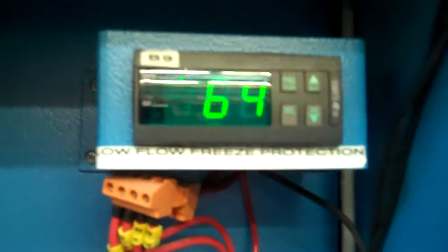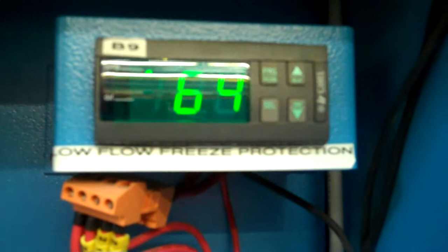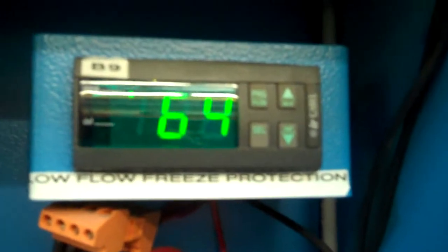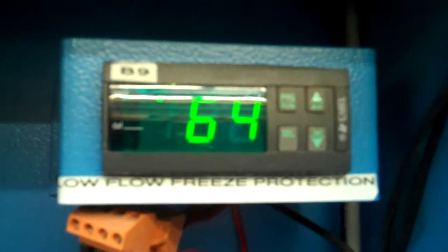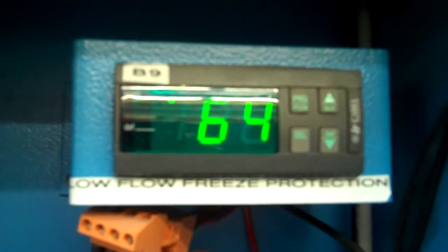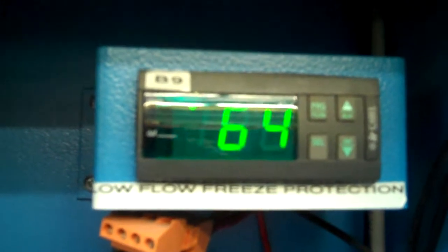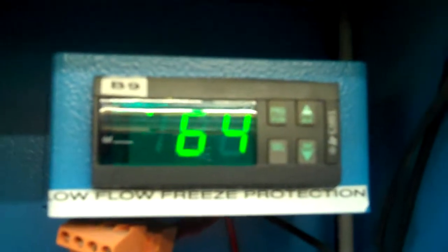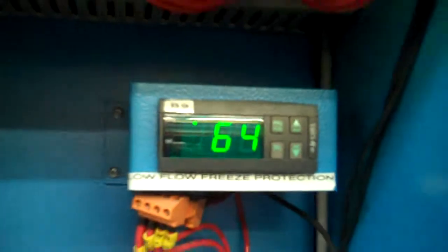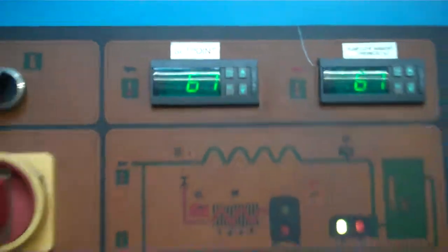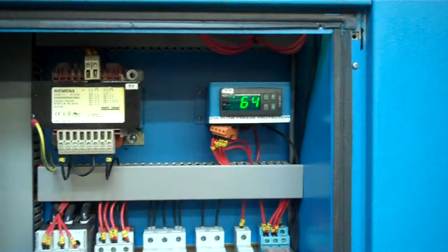Further inside the control cabinet is another temperature controller. You should not have to touch this one either. This is the low flow freeze protection, and that tells us if it sees a temperature that's too cold on the heat exchanger, which basically means it lost flow, it's going to shut the system down. So on these Carel temperature controllers, it's really only this one here, the set point, that you really should be worried about when you're ultimately running the unit.